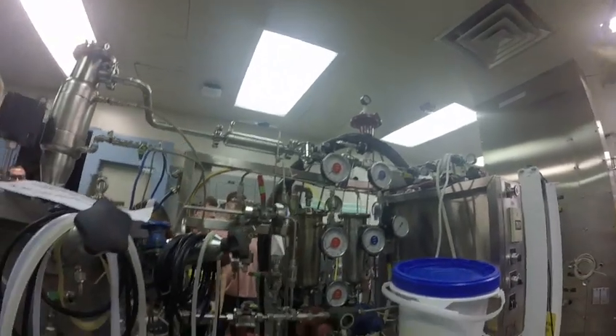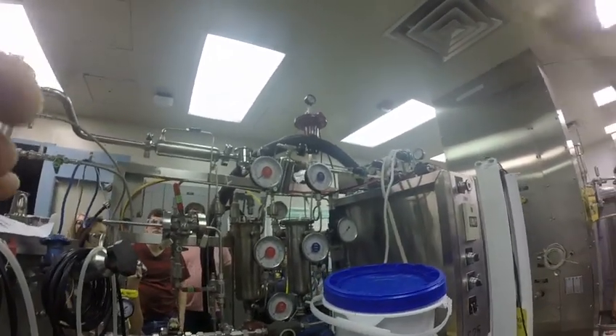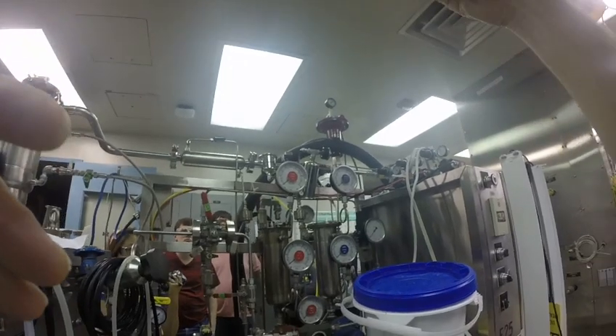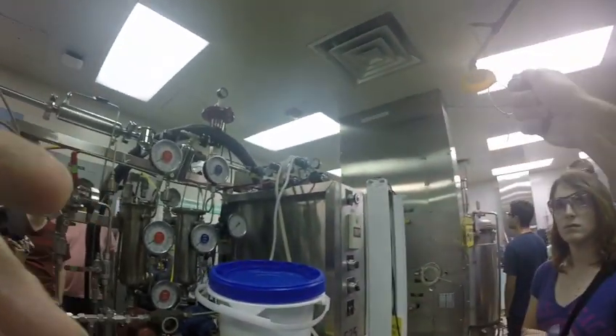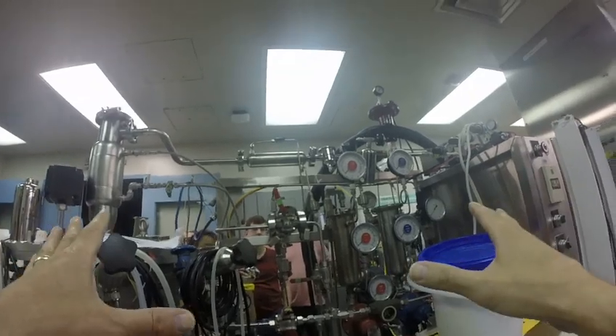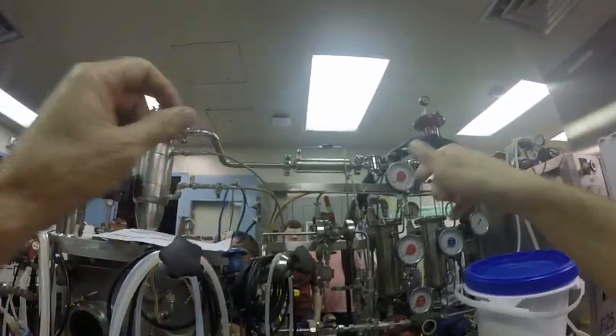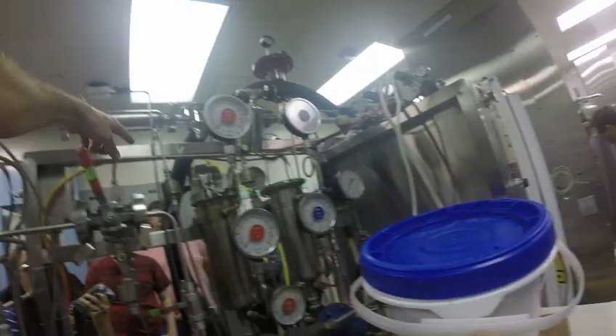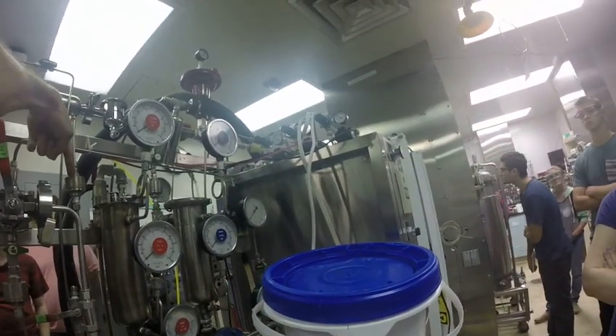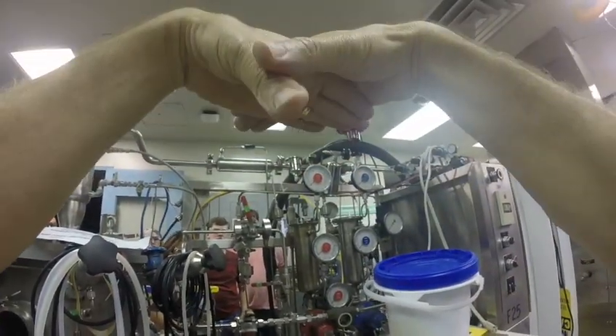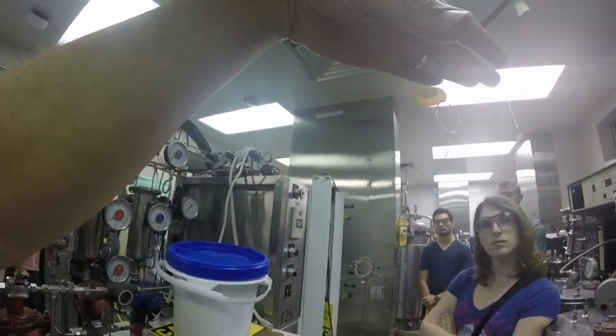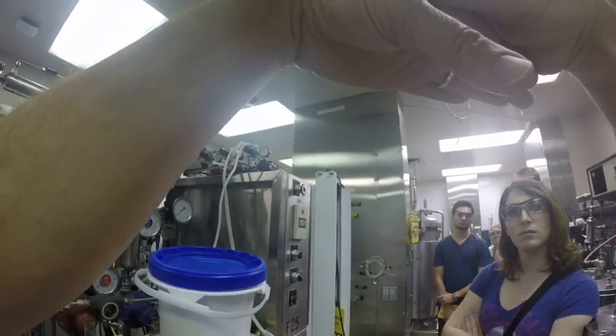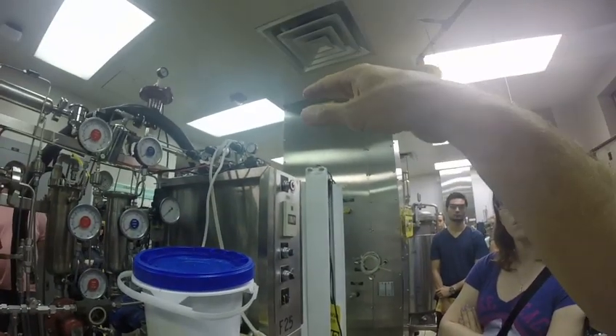And so on this unit, on the headers over here, there will be another Jordan valve, but it is a real steam pressure regulator that you set to the pressure at which you want to sterilize the unit. And then at any time in which I open a valve system and live steam comes and hits the steam trap, it will clamp down on it and not allow the steam to escape. What it does is that as the steam condenses, it'll drip down inside there, and when the condensate hits it, it actually cools it slightly, and then it'll just chatter open and spit out the condensate.